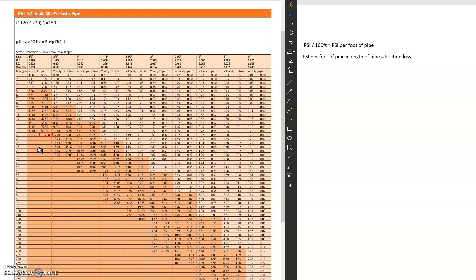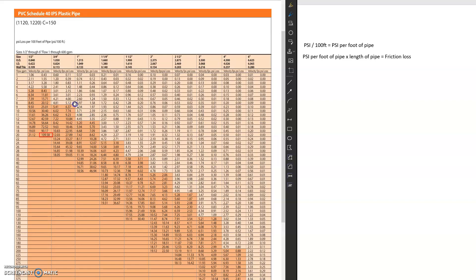And so we want to keep a lower friction loss, so we don't want to be losing 100 PSI. We don't want to be losing 8 PSI. We typically like to be in the, you know, 3 to 5-ish PSI per 100 feet is what we're looking at the standards as you can see here.